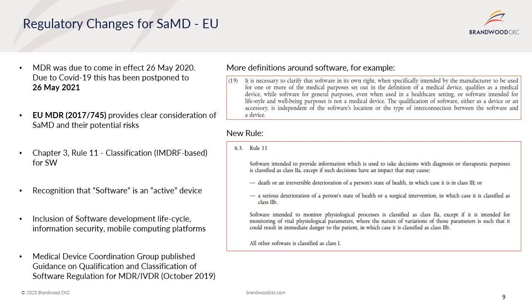We will now discuss some of the regulatory changes expected in the near future, specifically how they impact software as a medical device, starting with the EU. The new European Medical Device Regulations 2017/745, or MDR, came into force in May 2017 and was planned for implementation on 26 May of this year. However, due to COVID-19, this has been postponed to 26 May 2021. The MDR includes significant changes for software as a medical device by providing clear considerations of software and its potential risks. The MDR now includes clear definitions for software as a medical device, clarifying that software which operates in its own right and has a health purpose is a medical device, whereas software intended for lifestyle and wellbeing purposes is not.